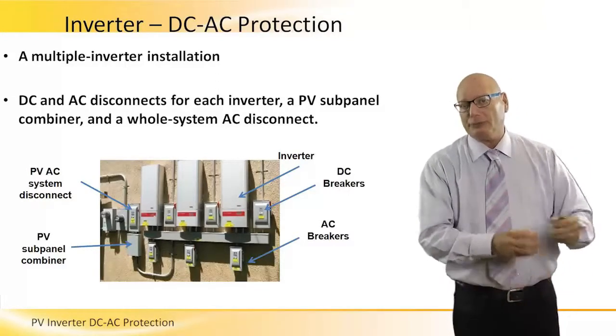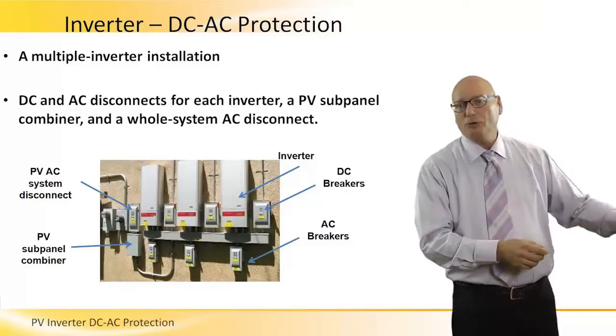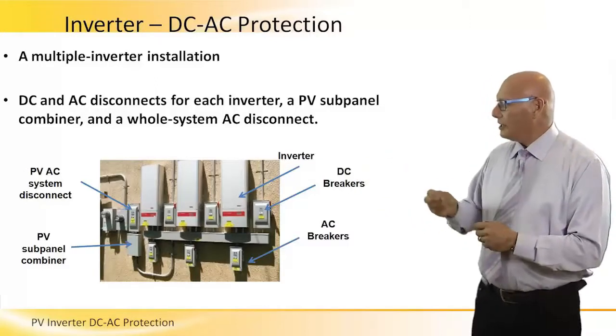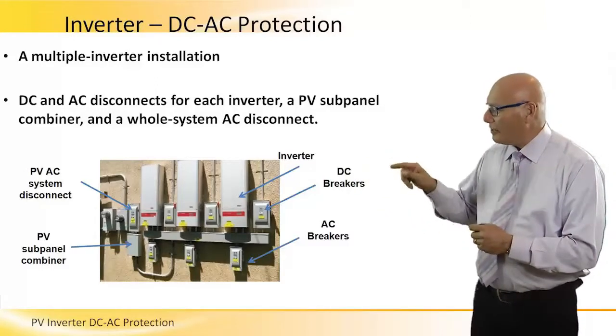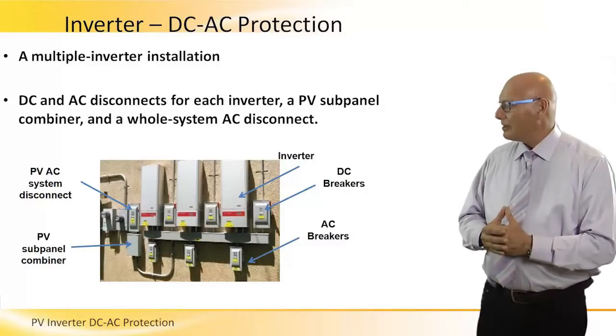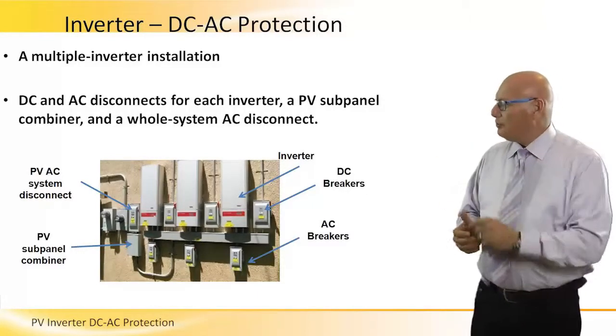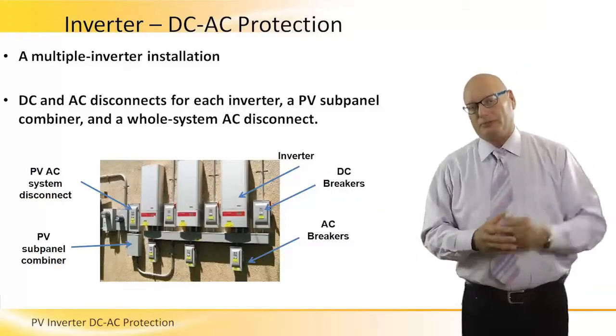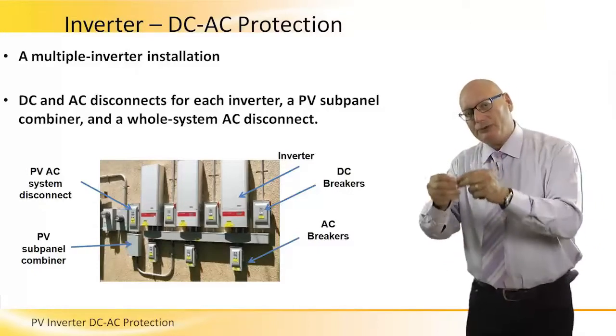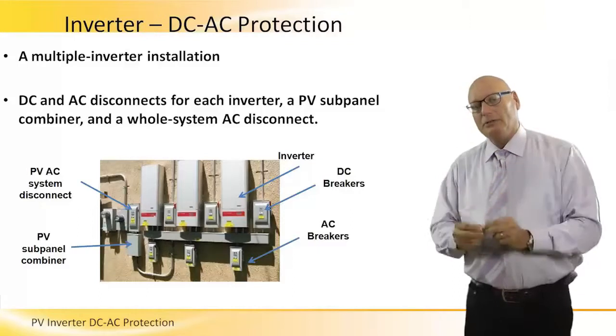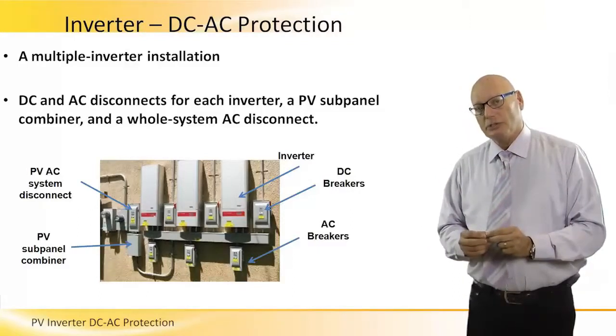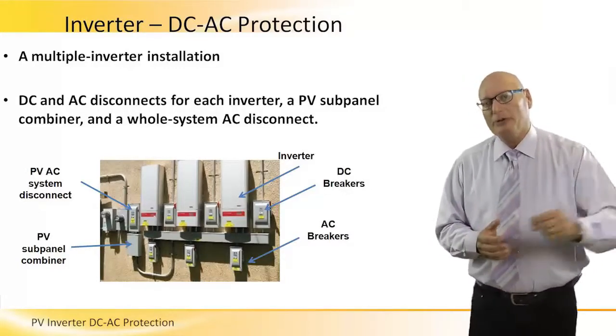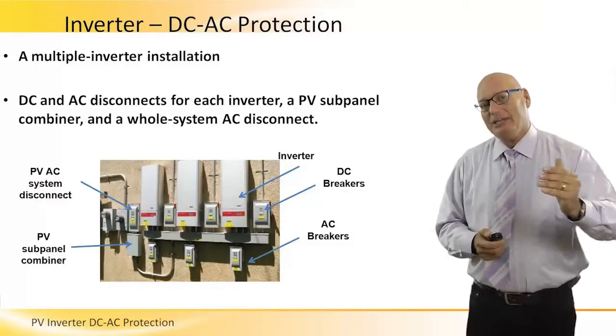Don't let these overvoltages and high-frequency voltages go to the AC lines. All three of these go to a PV sub-panel combiner on the bottom left corner of the picture. All of this goes to a PV AC system disconnect, to disconnect the entire PV system from the grid. So not only does each and every inverter have its own AC disconnect switch — after we combine all the AC together, we have a common AC switch, and then it goes out to the grid.